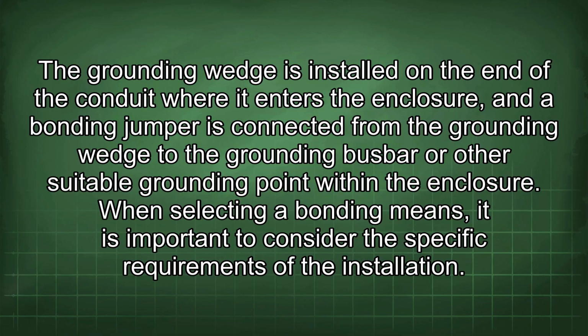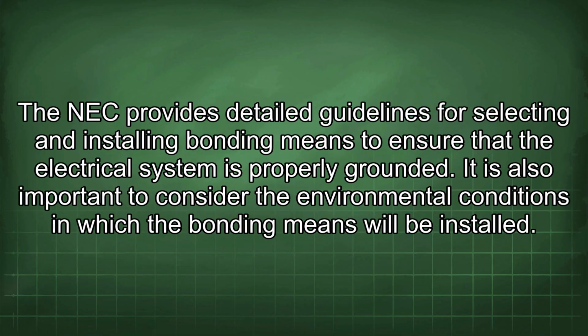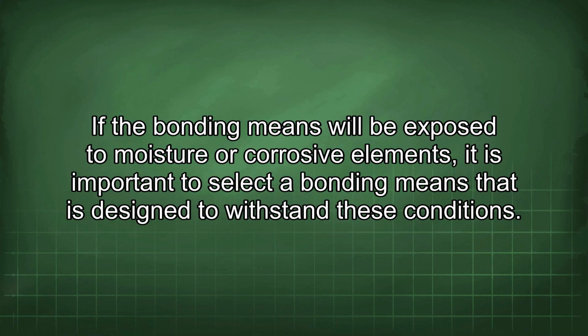When selecting a bonding means, it is important to consider the specific requirements of the installation. The NEC provides detailed guidelines for selecting and installing bonding means to ensure that the electrical system is properly grounded. It is also important to consider the environmental conditions in which the bonding means will be installed. If the bonding means will be exposed to moisture or corrosive elements, it is important to select a bonding means that is designed to withstand these conditions.